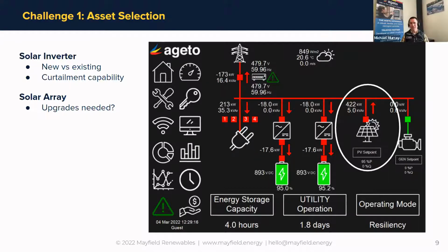Yeah, that's obviously very popular in the residential space, but most of the commercial inverters have curtailment capabilities over Modbus. So basically we just send the inverter a command saying reduce to 50% output, 40% output, and they'll adjust the power electronics internally to reduce the amount of solar allowed to pass through. They aren't actually burning it off or anything; it's just how they shift the power electronics inside the solar inverter. And that can happen on a second by second basis, so we balance the current facility load with the solar production every second.